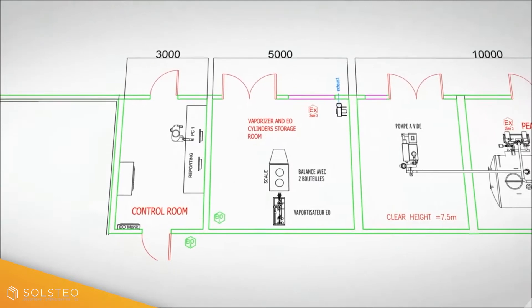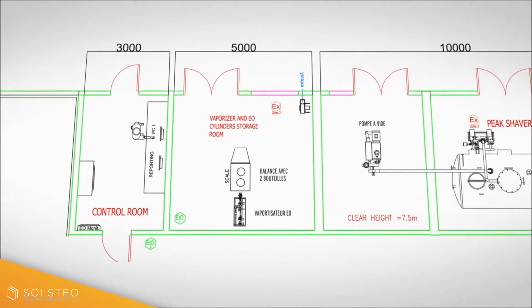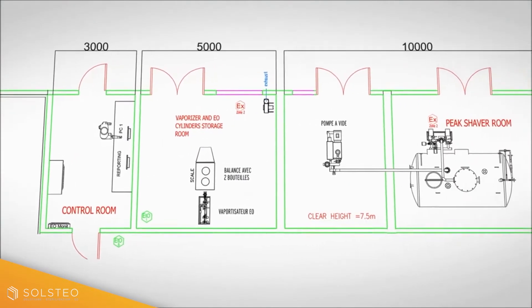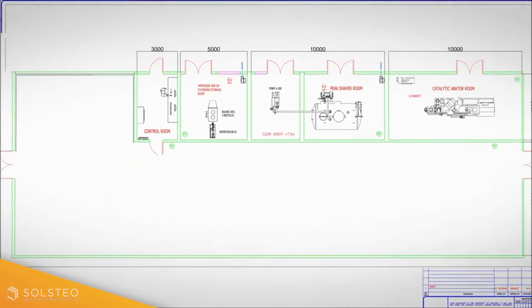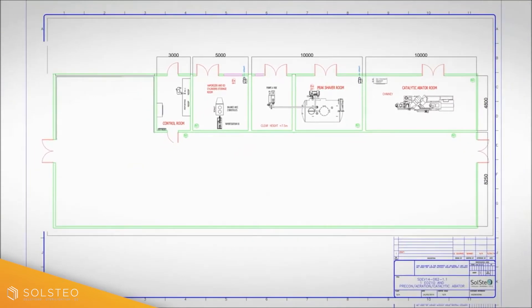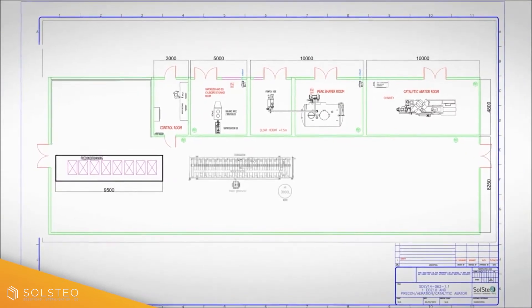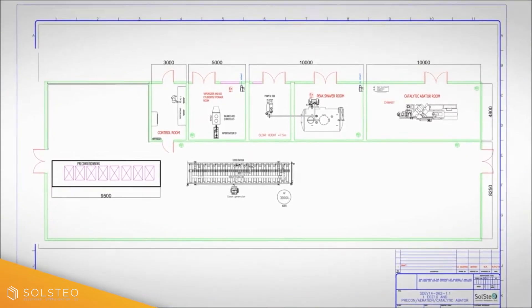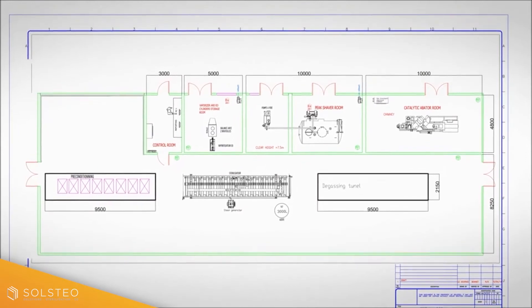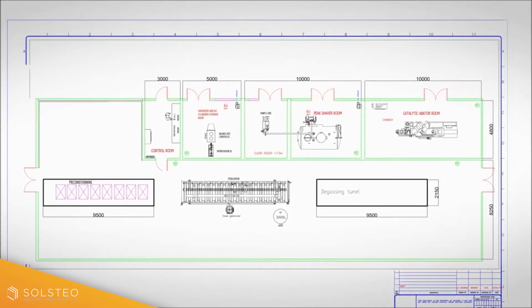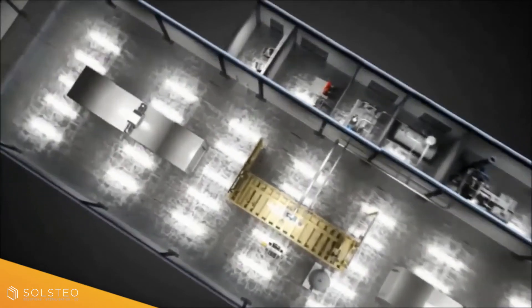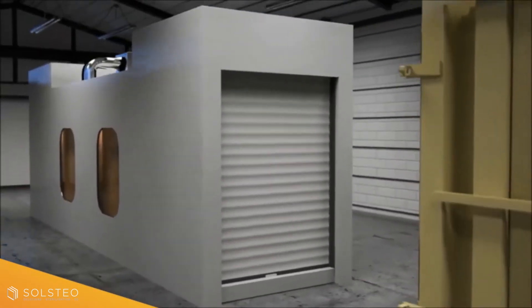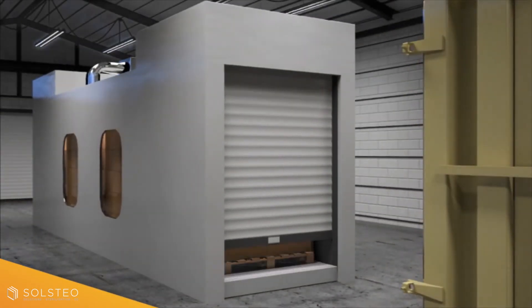A sterilization cycle typically lasts about eight to ten hours and can be divided into three phases: product conditioning, sterilization, and aeration. Let's focus on the sterilization step, after preconditioning where products are heated and humidified.